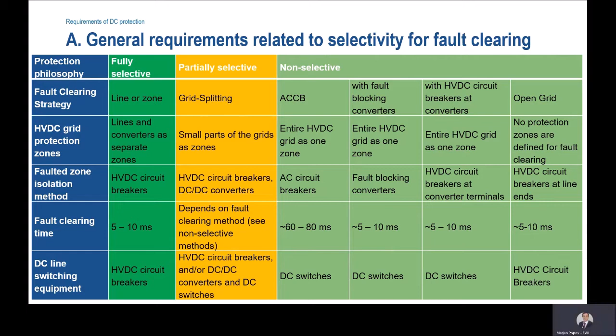Regarding the general requirements related to selectivity for fault clearing, they are based on several criteria, as can be seen in the first column of this matrix, denoted in blue. These are protection philosophies. Normally, protection schemes could be fully selective, partially selective, and non-selective. Thereafter we have fault clearing strategies, HVDC grid protection zones, faulted zone isolation method, fault clearing time, and DC line switching equipment. How these criteria are divided and depend on a different protection scheme can be seen in this matrix.